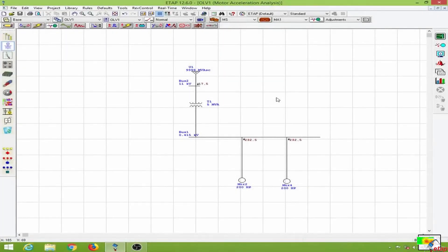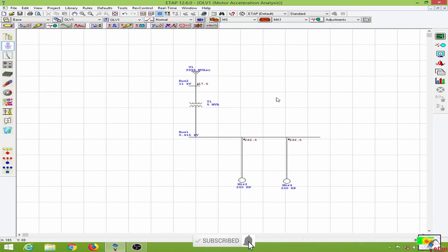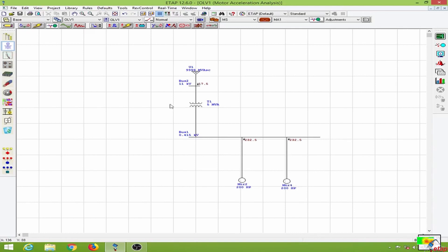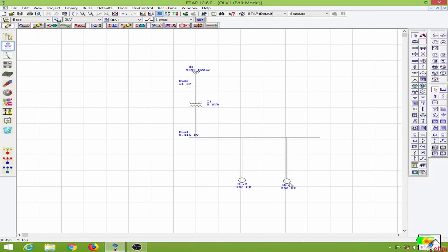In this lesson we will learn to provide a variable frequency drive to an induction motor and to start the motor smoothly using the frequency drive. In order to do the simulation, I will copy this 200 HP motor and compare it with motor 2, which does not have a starter, and motor 4, which has an autotransformer starter. Let me copy this motor over here.